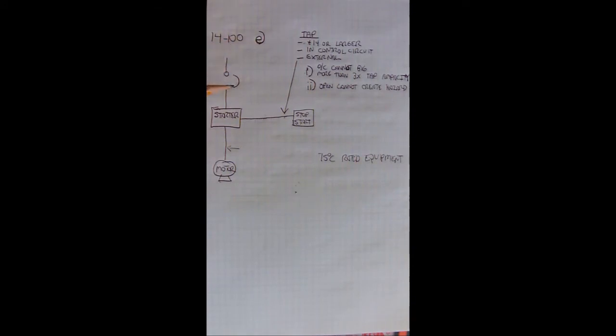So I have a circuit breaker, we got a motor starter, we have the control for the motor starter, a stop-start station here, and then we have a motor. All the equipment here, we're just going to do our standard default 75-degree rated equipment. So let's just recap the beginning of this rule, which basically says this conductor here is in the control circuit. It has to be a number 14 or larger, and it's external to the equipment, so it's not some pre-manufactured.